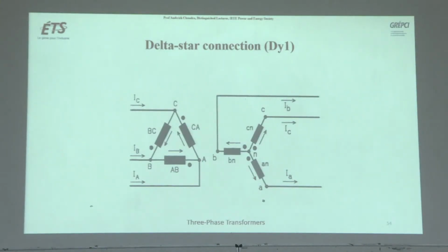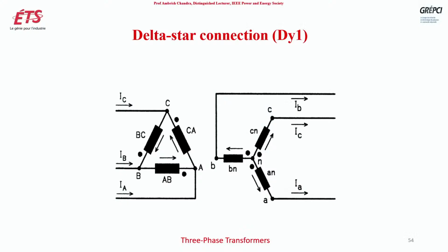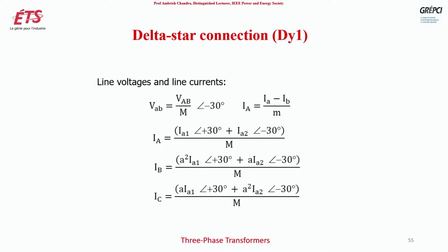Now, same way you can analyze DY1, which is also very popular in India also. DY11, DY1, these are popular transformers in India also. Okay, so engineers should know the characteristic of those transformers, and they have to choose which transformer is proper for your plant, what kind of harmonics are there, right? So this is just an example of DY1. And in DY1 we know the secondary side voltage is lagging behind 30 degree by the primary side voltage. That is why we have one here, right?